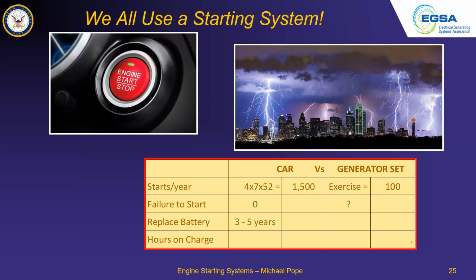Replace a battery on a car every 3 to 5 years, probably. I've been getting at least 5 years out of a battery before I need to replace it. On the generator set, if you're prudent, you will replace that battery on an emergency or standby generator set no more than after 3 years.